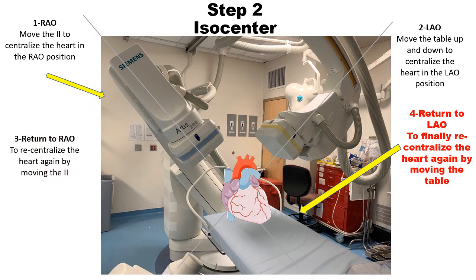Finally, we return to the LAO position to re-centralize the heart in the LAO position by moving the table up and down. After these four steps, we are now sure that the heart is in the isocenter of the two radiation beams.